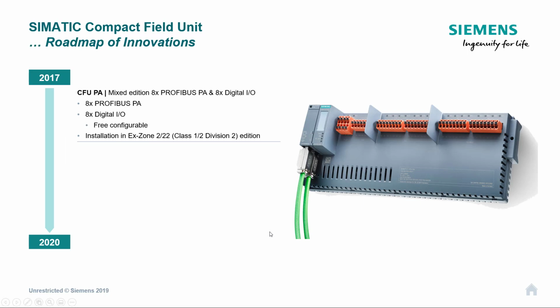So if we have a look at the history of the Compact Field Unit, the CFU came out in 2017. It is for use in zone 2 or 22 gas. Zone 2 or 22. That is probably its big limitation at the moment. We are waiting for the hazardous area version to come out, and I'm sure when that does, the conventional Profibus DP to PA will really start to die off, because of the advantages that you can have with plug and produce with this product. So I think it was towards the end of last year.